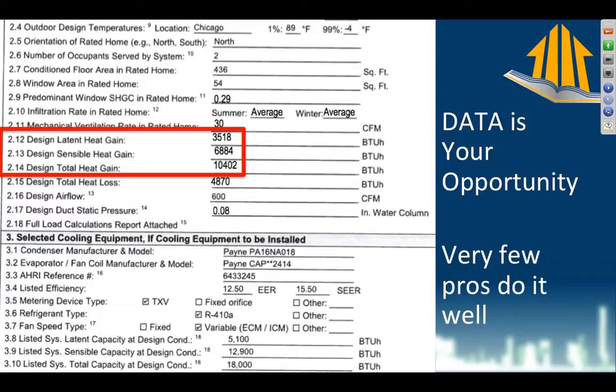Generally, what they are going to be is about 25% and about 75%. And you can see here we've got roughly 3,000, roughly 7,000. That lines up about with a 70-30 split is what we'd call that. Now, those two things add up to equal the total heat gain in the summertime. So the sun's beating down on the house, we've got some humidity inside, we have a total heat gain possible of 10,402 BTUs per hour. Now, based on that number, we are going to select down here at the bottom the equipment that matches that.